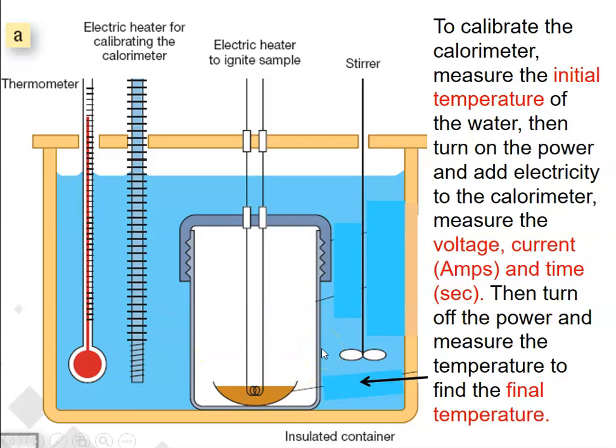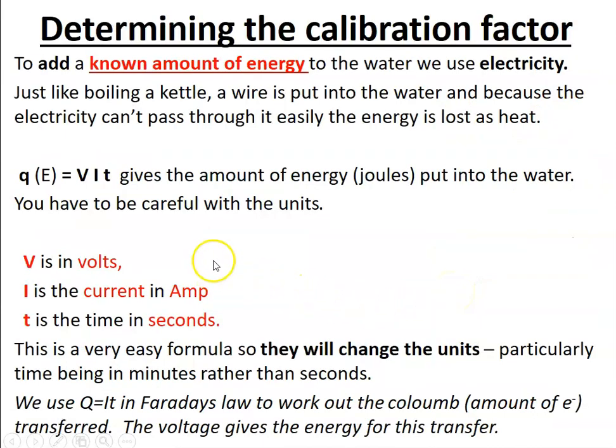And you know the amount of energy that you added to get that. So this is what I've been talking about—pause this, you could write this down. To determine the calibration factor, you have to add a known amount of energy, and we're going to use electricity.